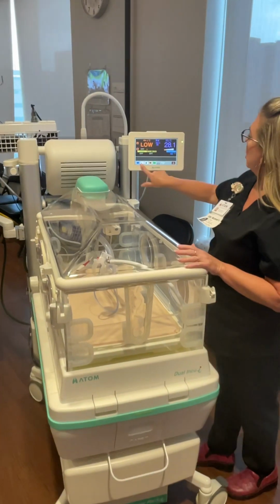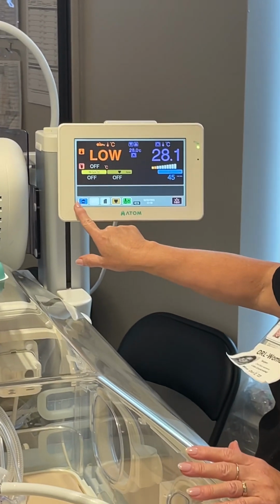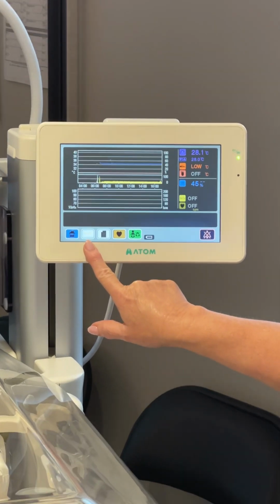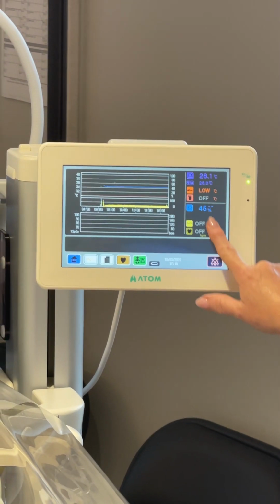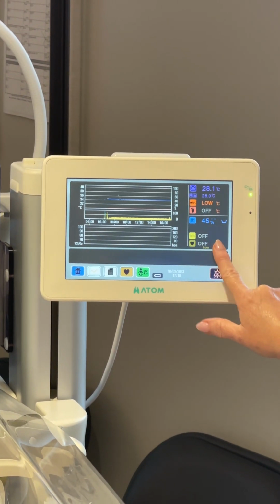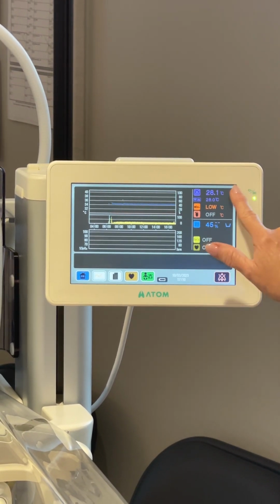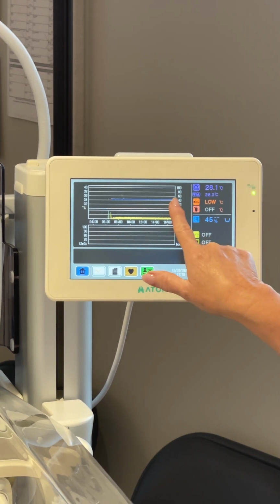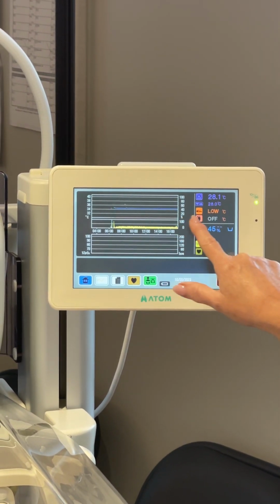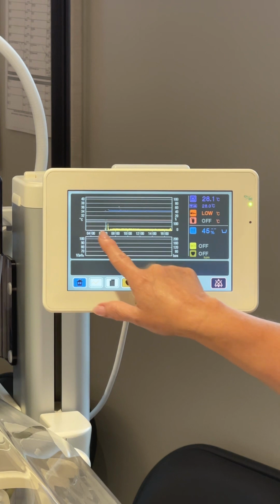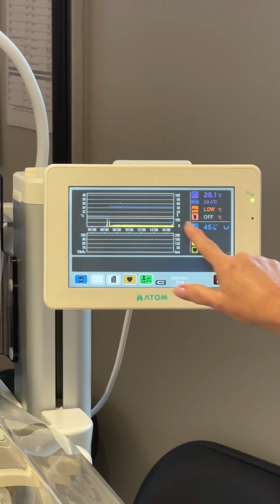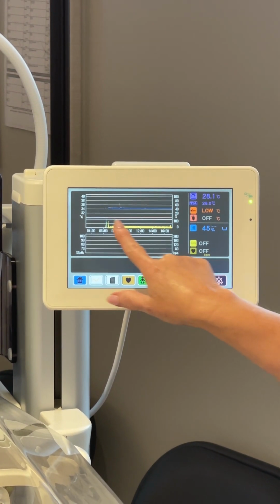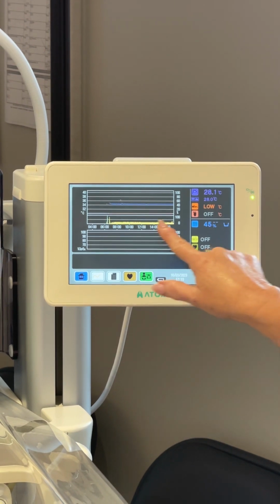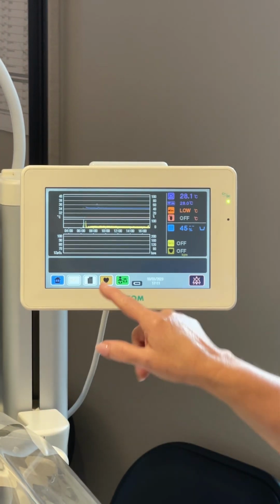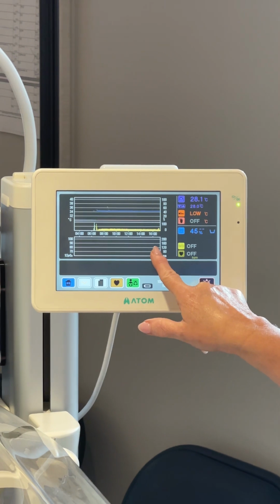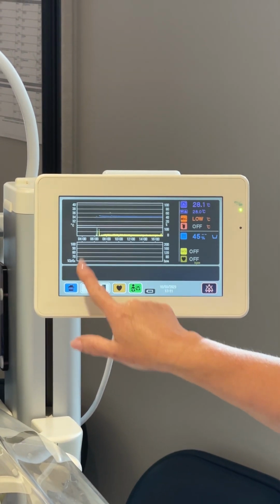Looking at the bottom menu bar, the second item is our trend screen. Patient information still appears on the screen to the right. On the trend screen, humidity is shown in blue, the baby's temperature in orange, and the heater in purple, so you can see how the heater responded or when it opened or closed. If we're using pulse oximetry, it would report here on the graph at the bottom.